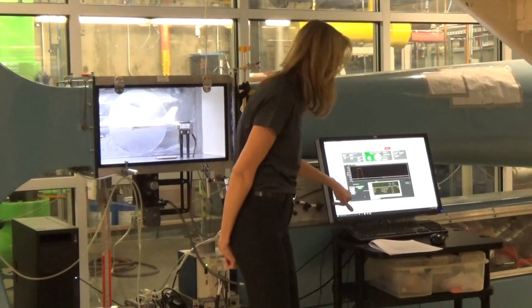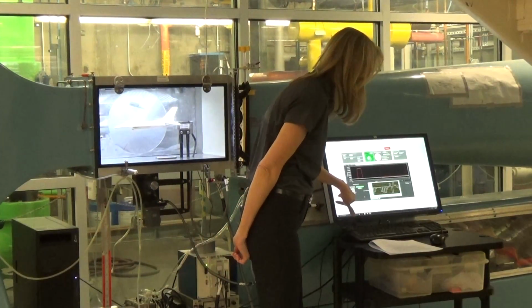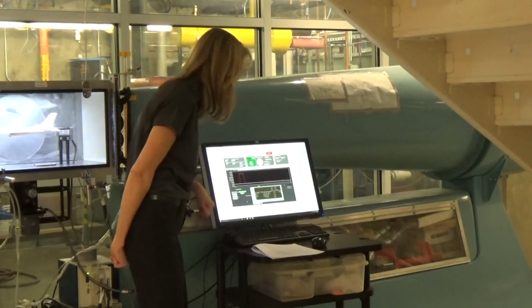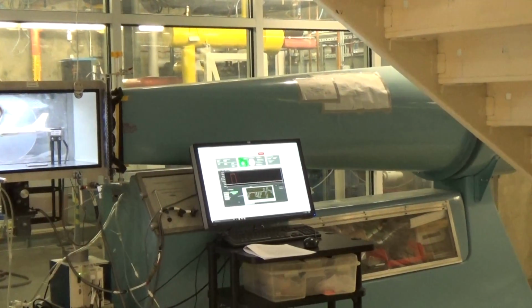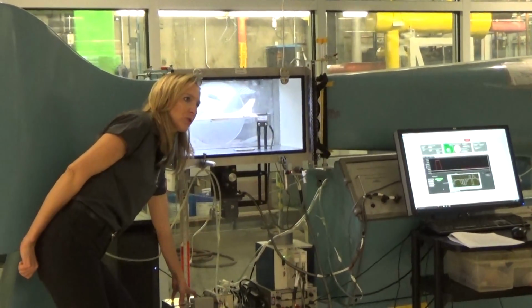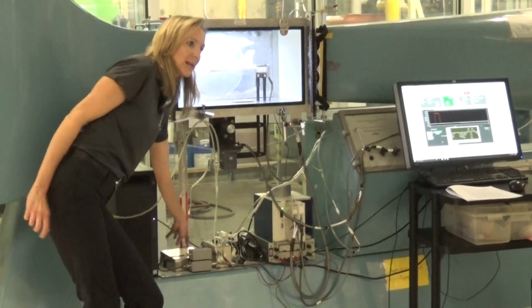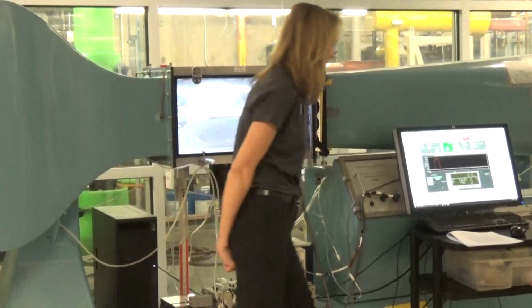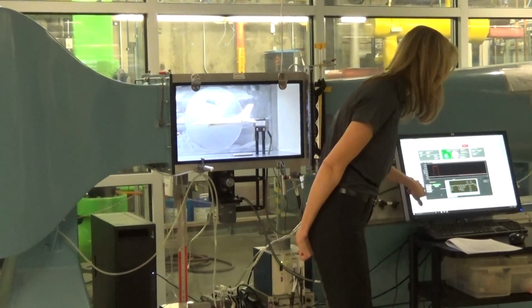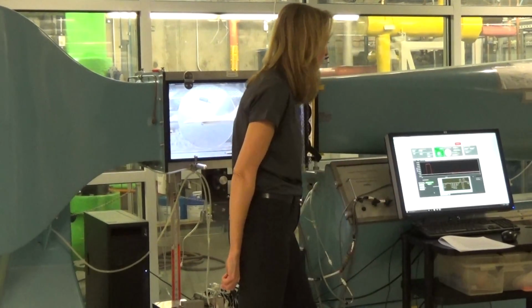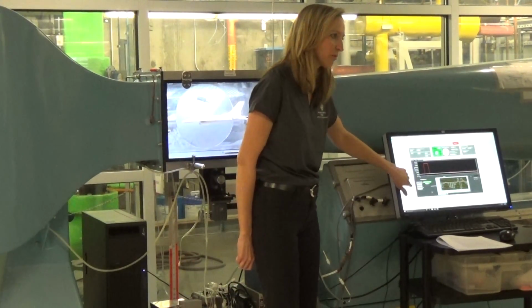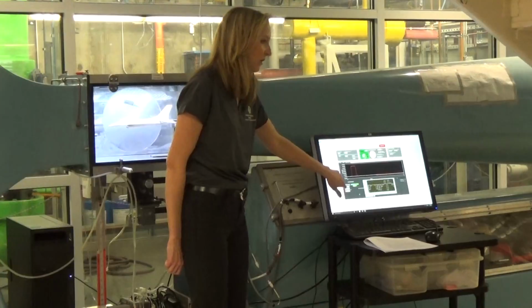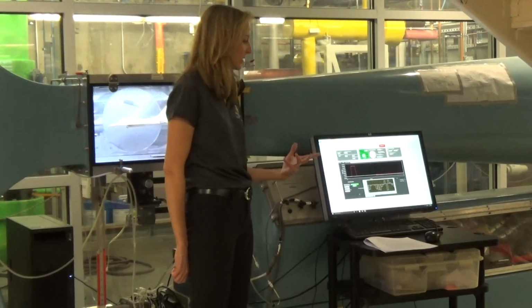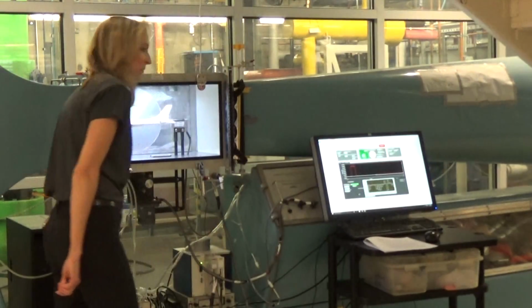Our density is displayed here using our atmospheric temperature and pressure measurements, which are inside this box. So that measures the room's temperature and pressure for today inside our room and gives you our density of about 0.95. So keep an eye on those and make sure that those are reasonable numbers. If they go outside of what you would expect, then something could be wrong with those sensors.